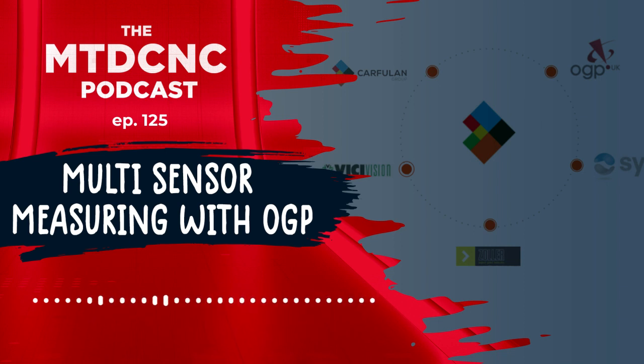No, well, you say that, but there's two ways of programming. One is what's called self-programming mode, so all you need to do is say I'm going to start here, I'm going to finish here, measure it for me. And it will select every feature that's possible to measure from the component it sees. Then you'll have to go and put your tolerance in.